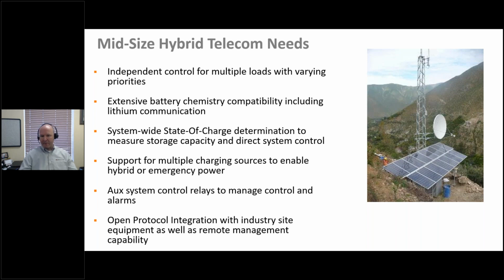So we provide a lot of that battery support through customization, through presets that can be saved, and through direct communication with lithium batteries that have a BMS interface, usually in either Modbus or CAN bus format. We provide that connectivity so we can read data such as state of charge, state of health, cycle count, and other communications right out of the battery directly.